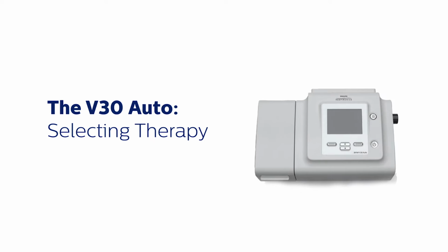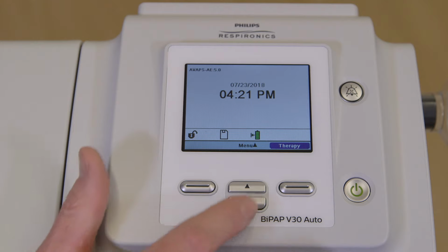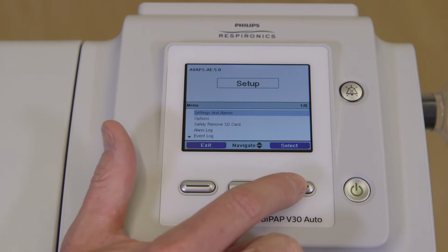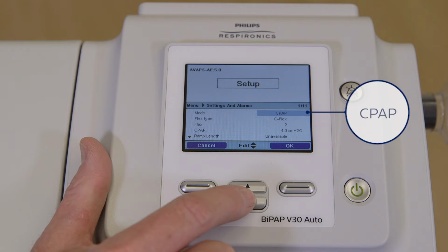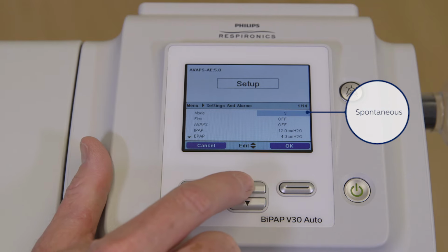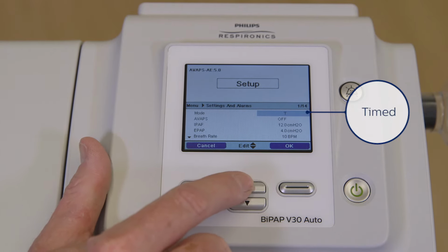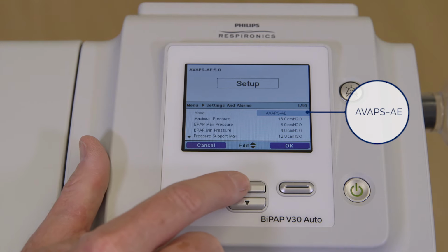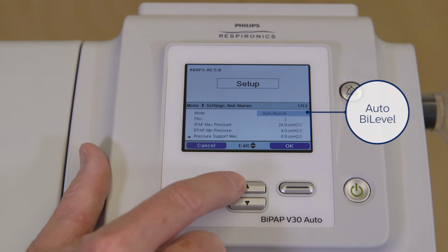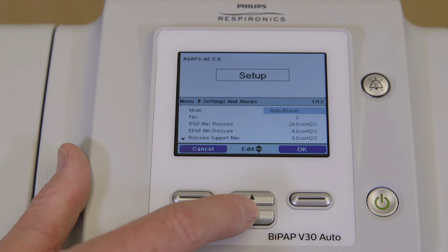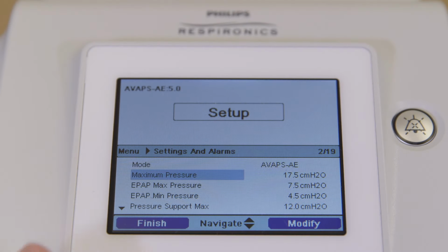When selecting therapy, the V30 Auto is able to provide clinicians a total of 9 modes to meet a variety of patient needs. This includes CPAP, bi-level modes, spontaneous, spontaneous and timed, and pressure control, as well as AVAPS AE and auto CPAP, auto bi-level, auto servo ventilation, or auto SV. With auto-titration, the device automatically adjusts EPAP, CPAP, and/or IPAP to meet the therapeutic target. As the user, you will define the minimum and maximum pressures for each patient.